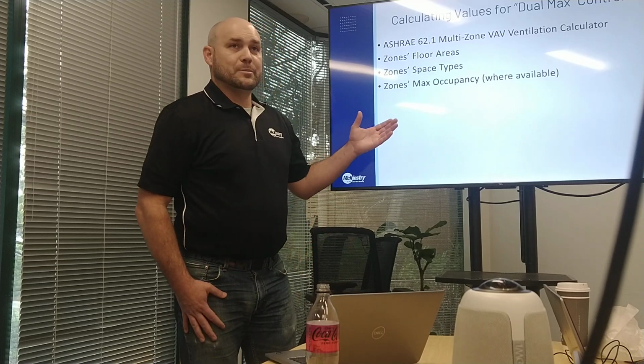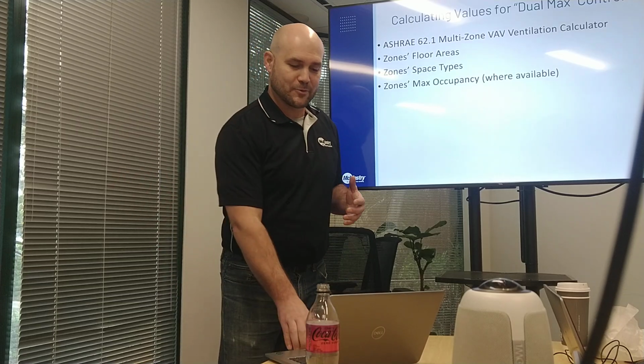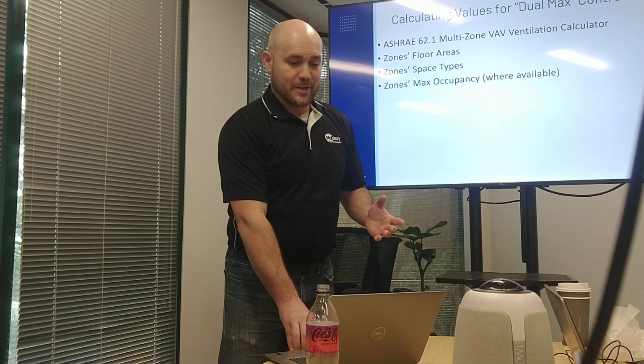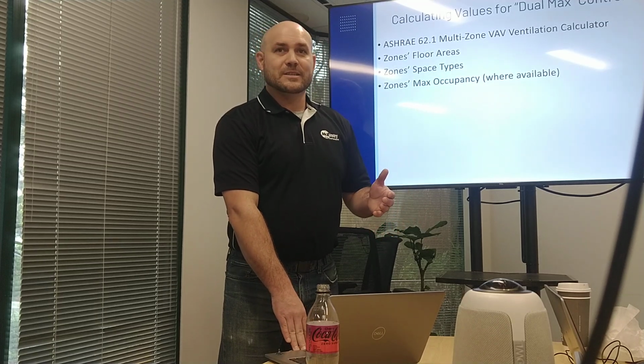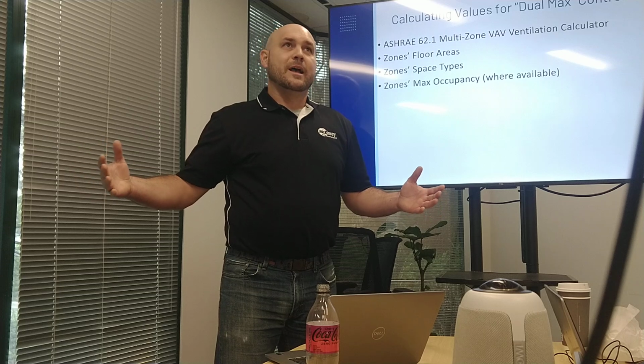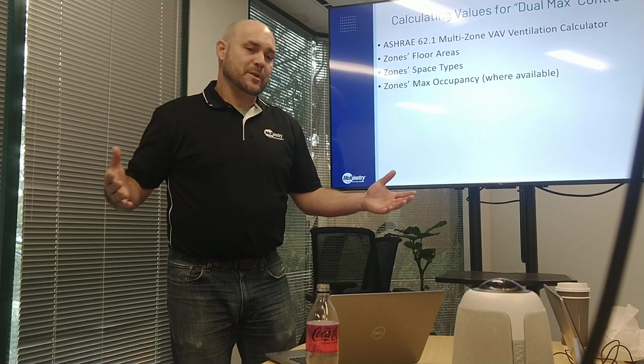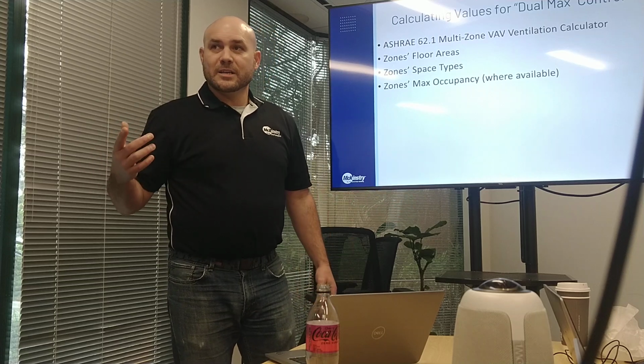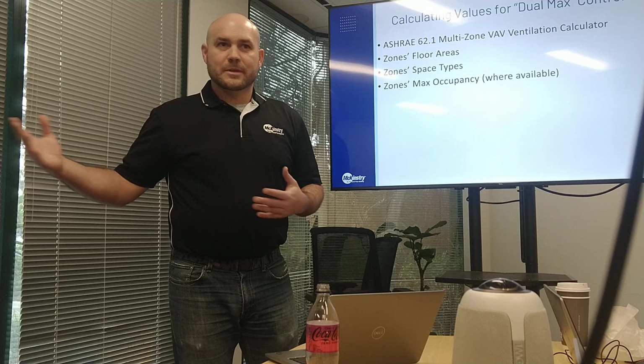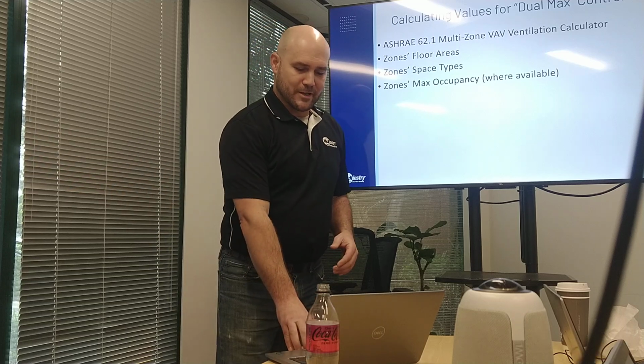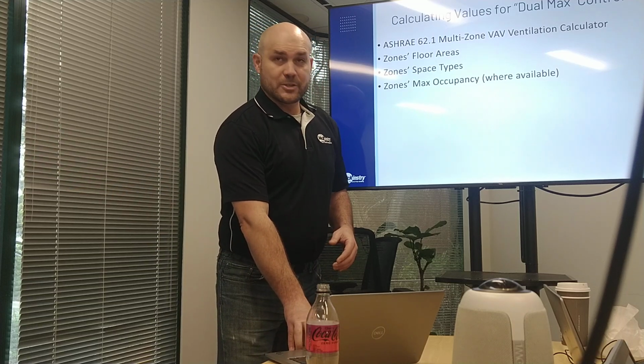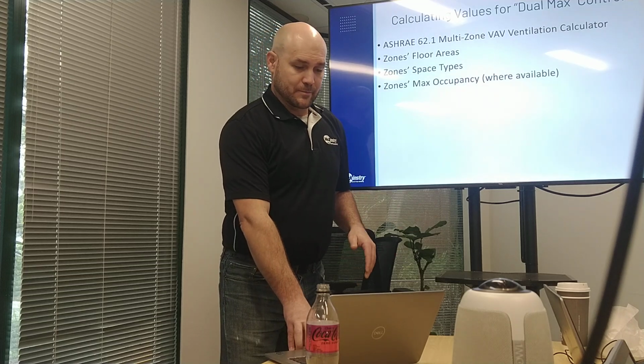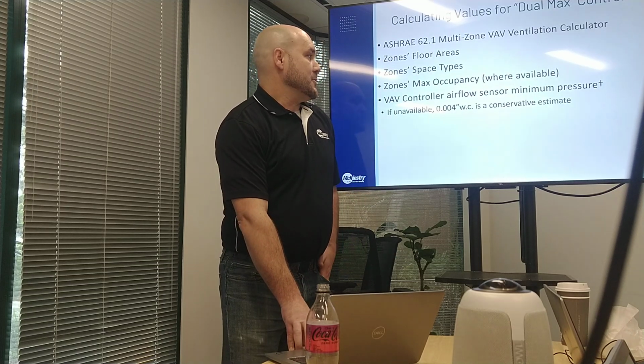But if there's a placard outside a room that says maximum occupancy, however many people, snap a picture of that. It's really useful. That's more definitive than saying, oh, it's a 1,000 square foot room and the default occupancy is 35 people per 1,000 square feet, so there's going to be 35 people in there. Well, if the placard outside says 45, then that's going to make a difference in what the ventilation requirements are for the space, which dictates how low you can actually set those minimum values.